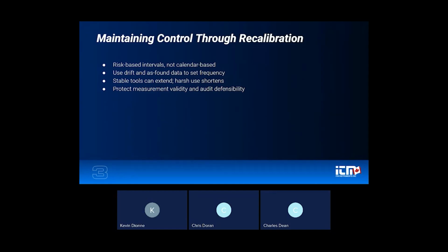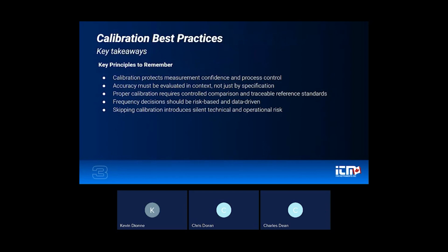Ultimately, recalibration isn't about meeting a prescribed schedule. It's about maintaining measurement validity, controlling uncertainty, and ensuring that your data remains reliable for its intended use. So, calibration protects measurement confidence and keeps your process under control. Accuracy isn't just a number on a data sheet. It has to make sense for your application. Calibration is a controlled comparison, and it only works if your reference is accurate and traceable. Calibration frequency should be based on risk and real performance data, not just a date on a calendar. And finally, skipping calibration doesn't cause immediate failure. Well, sometimes it does, but it doesn't always cause immediate failure. It introduces silent risk that builds over time.